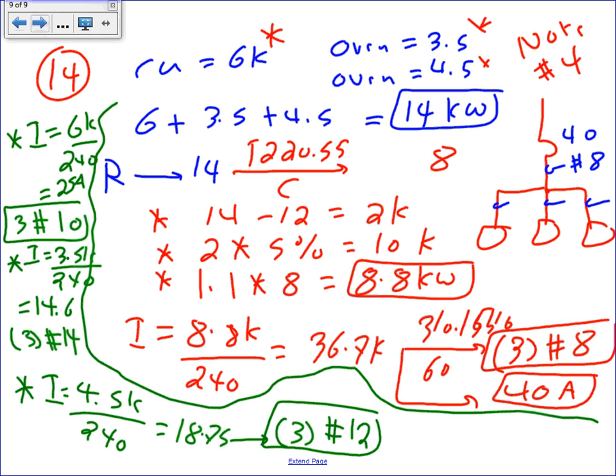So these conductors, guys, what did we say? This is 6, this is 3.5, and this is 4.5, and the 6 was number 10, right? And this one, the little guy, was 14, and this guy was 12. Is that okay? Tapping them, no problem, in the same area, same proximity. So you bring number 8, and you put it in a box, and you tap these conductors to feed these 3. Only acceptable if you're using them in the same room.